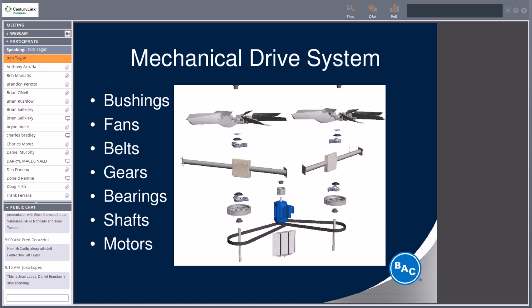Typically on a cooling tower, on a retrofit or preventative maintenance, you're looking more at the bushings, bearings, and the belts. Typically, in most operations, your fan shaft has a pretty good longevity, lifespan. It's really the bearings and the belts that you need to be worried about. If a cooling tower operates too long with a belt that's out of alignment, obviously you can have damaged bearings.